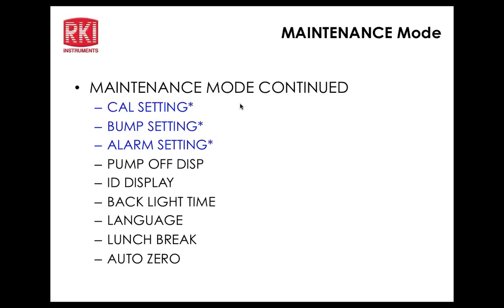Let's look at bump parameters. Gas time is 30 seconds. The check is plus or minus 30% of the cal value, which is the variance the bump will allow. The cal time will be 90 seconds. So if you fail a bump, it will calibrate, but when it calibrates it just adds 60 seconds of cal gas to that calibration time, so the total time is actually 90. Right now I have auto cal on, so if the bump fails, the unit will automatically initiate a calibration, as long as the gas is flowing and you haven't touched anything.